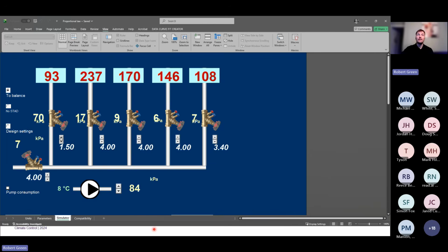And you can see I'm able to see the flow in all 5 of these pretty easily. And let's come back up again. Let's decrease that. Okay, we're good. This one's at 200%. Try and adjust this down. And we can see flows are changing throughout this system in what seems, if you've not been paying 100% attention, a fairly random manner. And iteratively, it can become a real nightmare to try and set this system up. We're having to scope between 5 different devices. And as I said, relatively speaking, this is pretty easy because I can see live the flow in all of these 5. And how often are you balancing a system with only 5 devices on there?